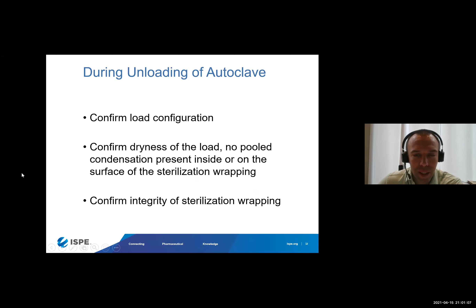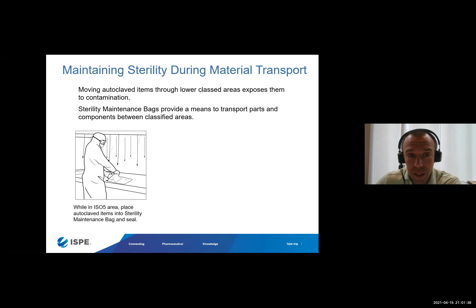There's an option here to have a secondary protection of the sterilized parts. We call this a sterility maintenance bag. This is a 100% poly bag, which is 100% impermeable, a complete microbial barrier. This is an option for transport and storage where we're placing materials directly from the autoclave into this sterility maintenance bag, typically in an ISO 5 area.